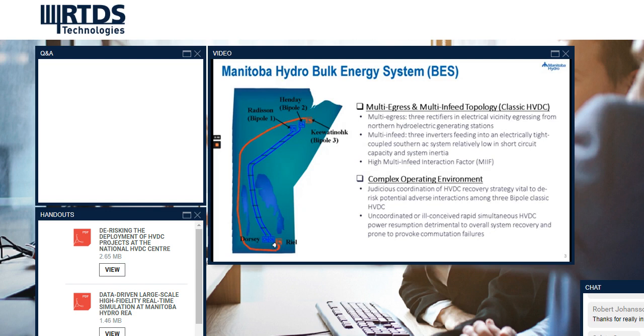The newly inaugurated Bipole 3 HVDC, with classic LCC technology, traverses 1,400 kilometers in a west corridor strategically separated from the interlake corridor. It originates from the Keewatinohk rectifier station in the north and terminates at the Riel inverter station in the south. Together, Bipole 1, 2, and 3 transmit about 80% of Manitoba Hydro's annual energy portfolio from its northern hydro stations on the Nelson River to southern load centers and export markets.